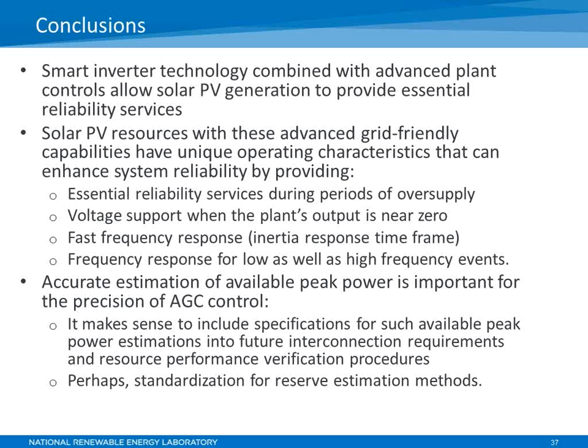The project showed how solar PV generating plants can provide a wide range of essential reliability services, and demonstrated fast and accurate PV plant response to AGC, frequency, voltage, power factor, and reactive power signals under a variety of solar conditions. To maintain an adequate level of reliability through the transition to high penetrations of variable generation, all resources need to provide sufficient voltage control, frequency support, and ramping capability. These are all essential components of a reliable bulk power system.